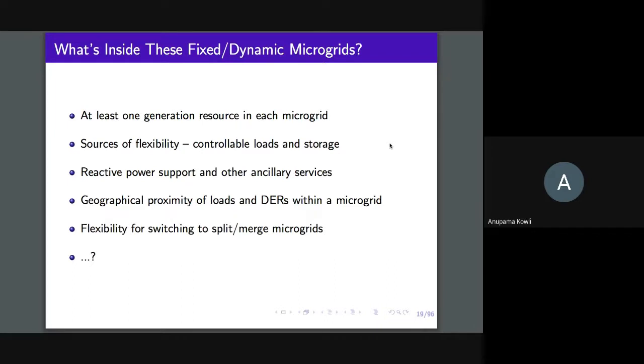For sure, if it's a microgrid, then there has to be at least one source in it, so one local supply has to be there. There has to be at least one sink in it, so there has to be one load, so to speak. In addition to this, you would still need other things. You have to think of, if you were to island, how are you going to manage the supply and demand, which means you may need some sources of flexibility in terms of storage or loads that are flexible and so on. You need reactive power support. More from a power engineering perspective, we need ancillary support in terms of reactive power support, VAR support, and so on.